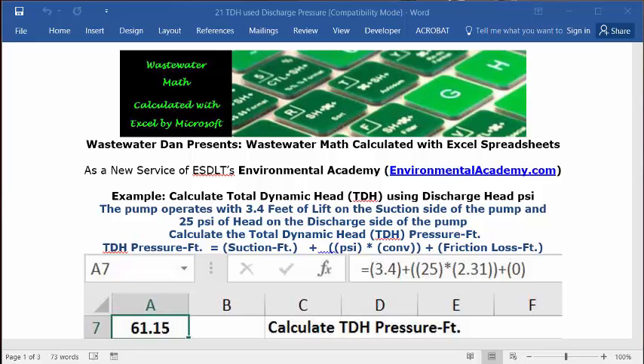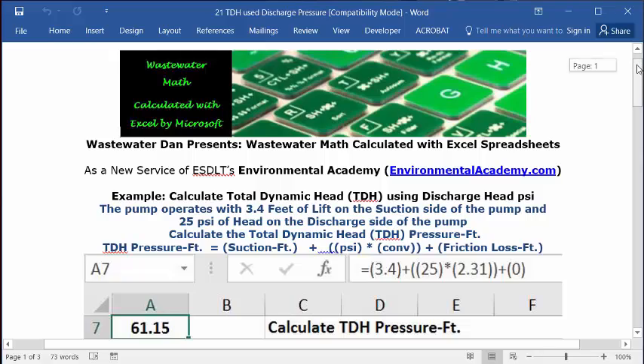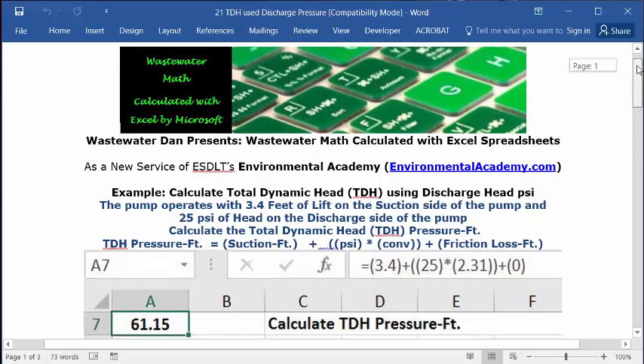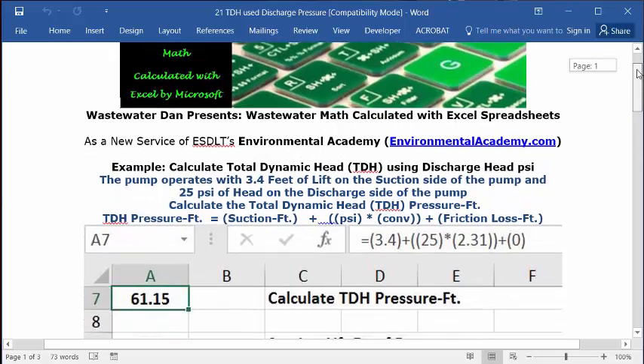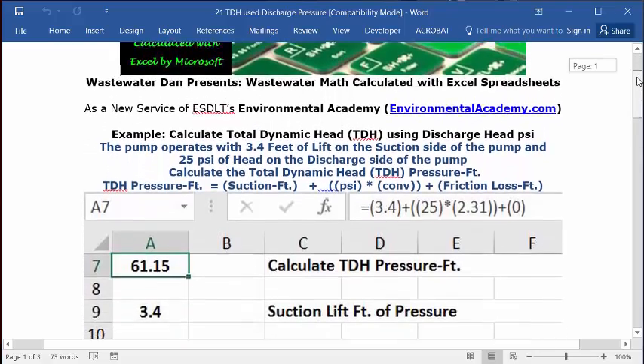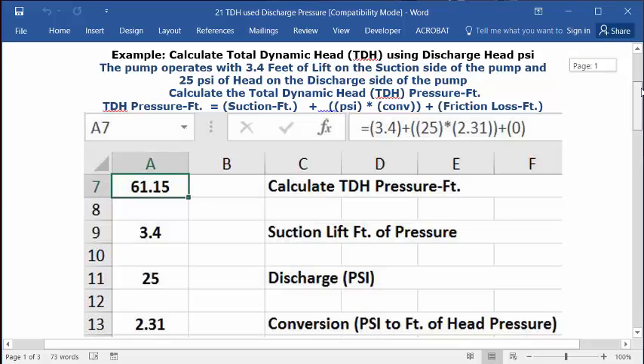Today's solution uses the following formula. TDH pressure in feet equals suction lift in feet plus PSI times the conversion factor from PSI to feet of discharge plus friction loss. So all three of these dimensions will be entered ultimately as feet, added together, and that will equal our total dynamic head, our TDH.